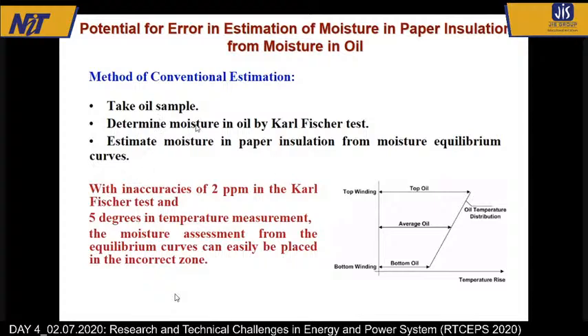But then there is some problem here. What is that problem? That these curves are temperature dependent. Now, typically, if you look at the winding temperature and the top oil, they don't have the same temperature. So therefore, which temperature should I take? Generally, on transformers, if you go and see, there will be two thermometers. We call them top oil temperature and bottom oil temperature. We take these two readings.